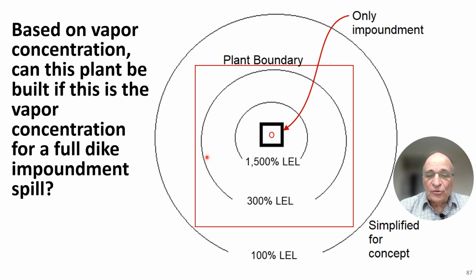This line is 300% LEL. This line is 1500% LEL. Now you might say, how can you get 1500%? Well, how can you get 300%? Well, what is 1 LEL, or 100% LEL, I should say? That's 5% gas. So 300% LEL would be 15% gas. 1500% LEL would be 75% gas concentration.